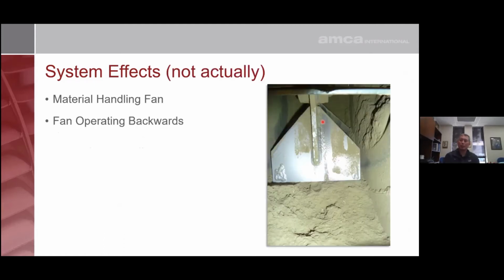This is not really a system effect, but this slide is just to remind everybody, centrifugal fans do move air in the proper direction, even if they're running backwards. When you're hooking up a three-phase motor to a fan, you have roughly a 50-50 shot of that motor running in the proper rotation. So you hook it up, you bump the starter, and you should look and see if the wheel is rotating in the same direction as the rotation arrow of the fan. If you don't check it and you use your hand to feel air blowing out of the outlet, that's not the best way to do it. You're going to be wrong half the time.